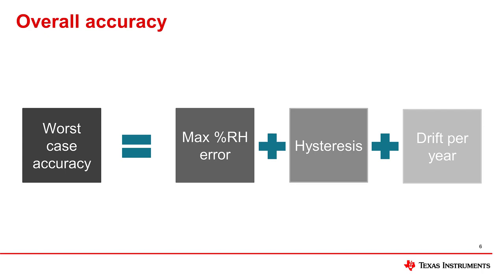Some datasheets will specify a maximum percentage relative humidity that includes hysteresis, while others will leave it as two separate values. However, it is important to understand the individual components of system accuracy. This worst-case accuracy applies to the HDC3X family of relative humidity sensors.